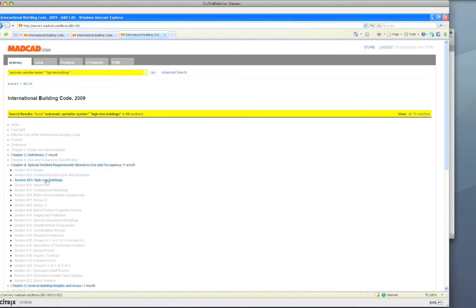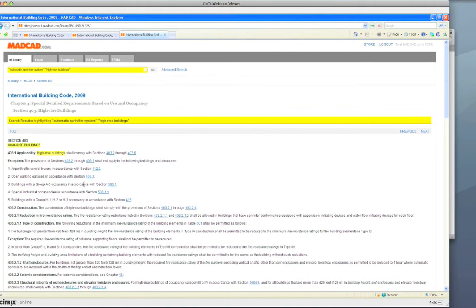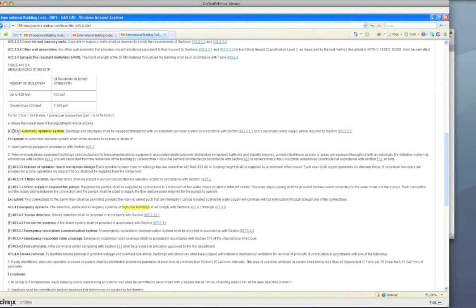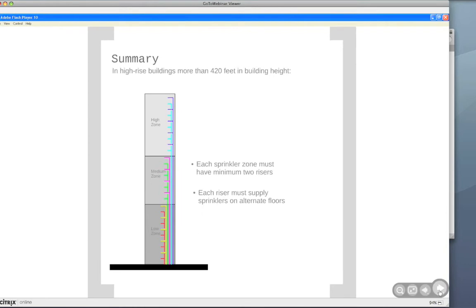I'm going to jump to section 4, section 403. As I scroll down in section 403.3 automatic sprinkler system, I can note the new changes for the number of sprinklers and system design. According to the new section 403.3.1, each sprinkler system zone in buildings more than 420 feet in building height is required to provide a minimum of 2 risers. Now I'm going to jump back to the presentation again, where we provide an illustration and summary for this change. So in summary, in high-rise buildings more than 420 feet in building height, each sprinkler zone must have a minimum of 2 risers, and each riser must supply sprinklers on alternate floors.